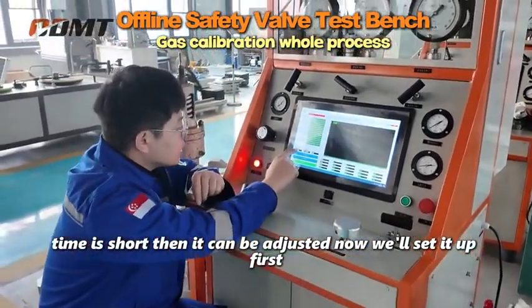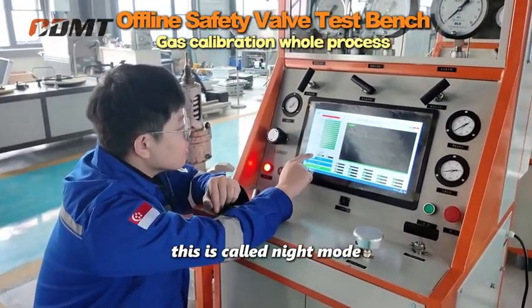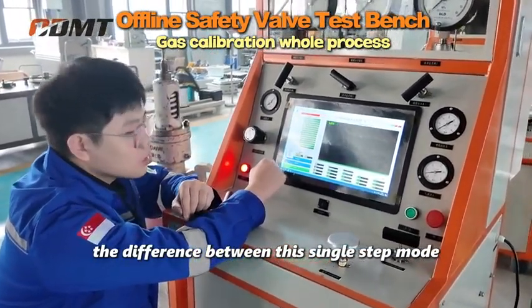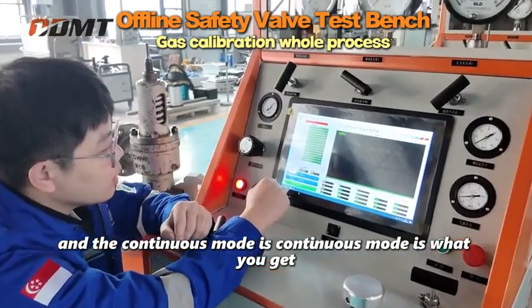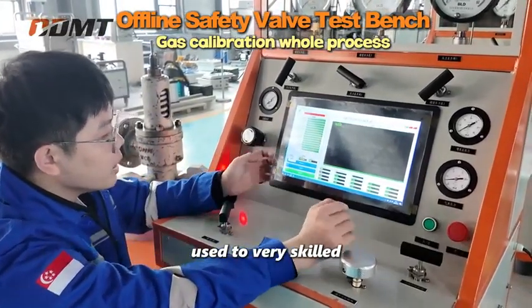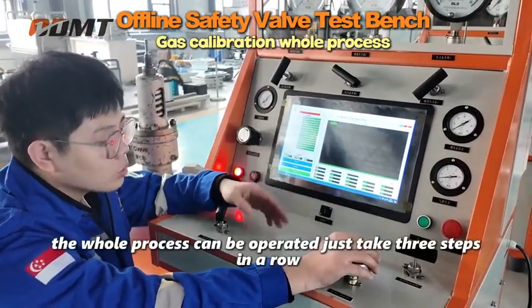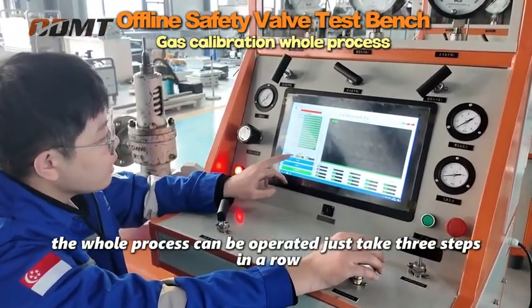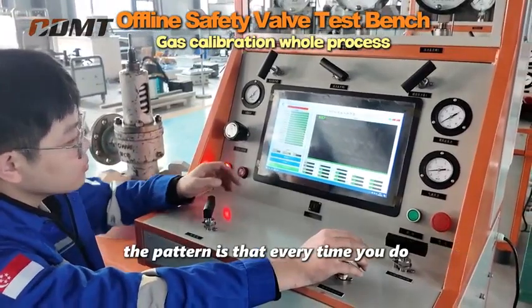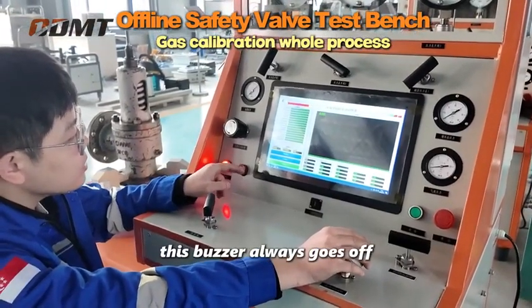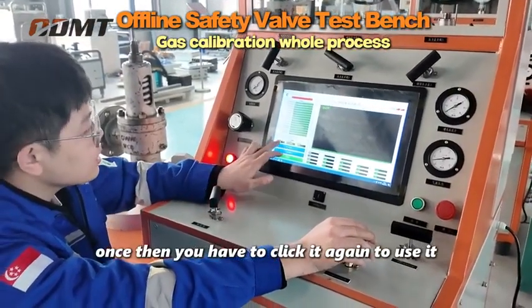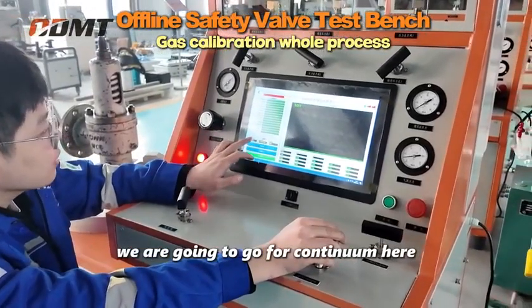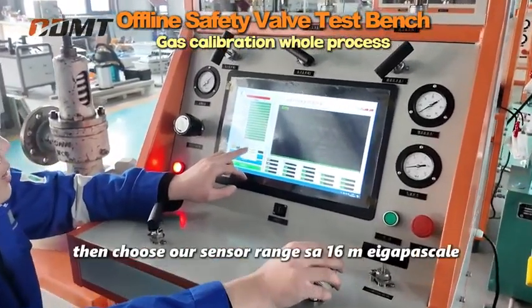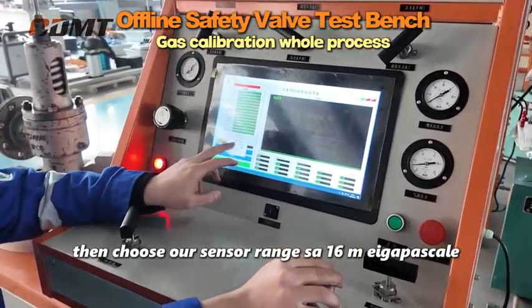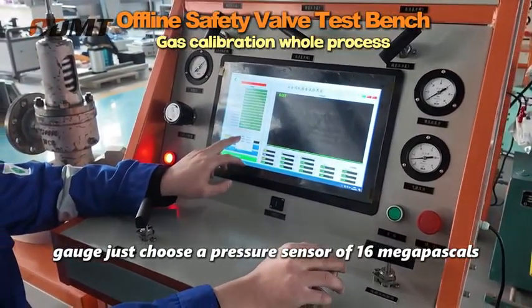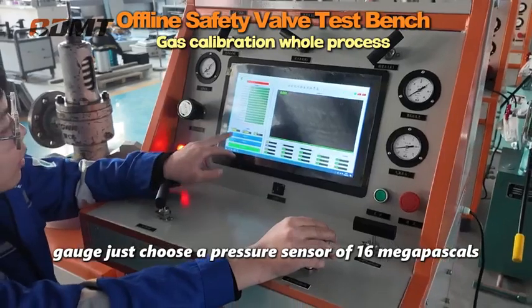We'll set it up first. Then there's the operation mode. The difference between the single-step mode and the continuous mode is that continuous mode is for when you are used to the process and very skilled. The whole process can be operated, just taking 3 steps in a row. In single-step mode, every step, the buzzer goes off once, and then you have to click it again to continue. We are going for continuous mode here. Then choose our sensor range. It's a 16 megapascal gauge, so just choose the pressure sensor of 16 megapascals.